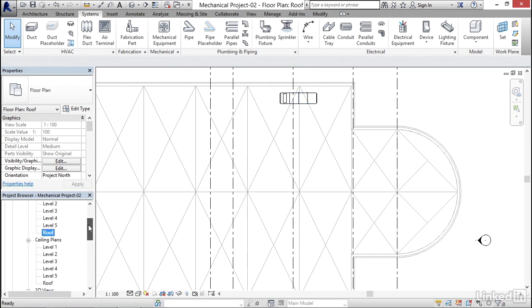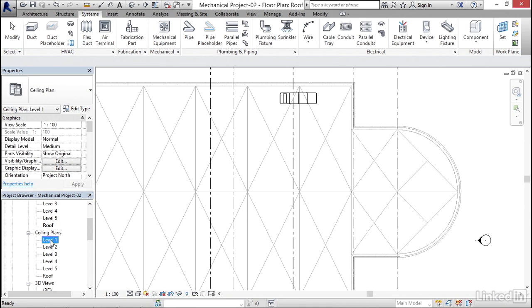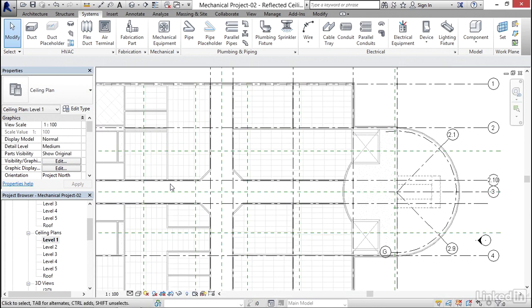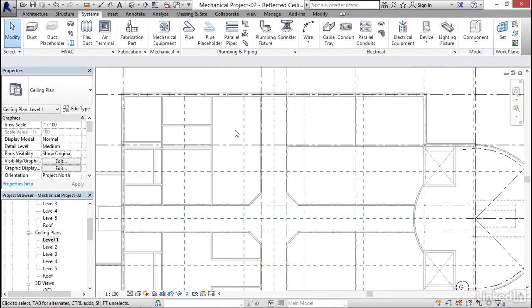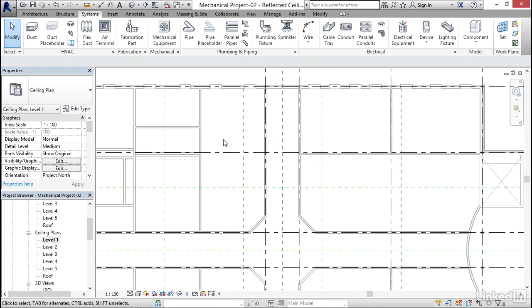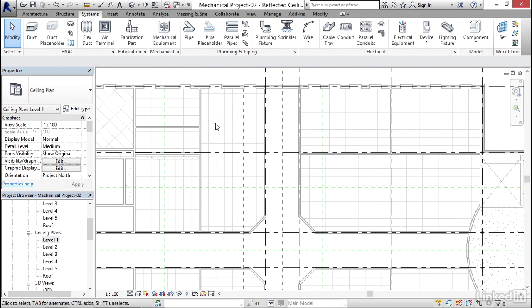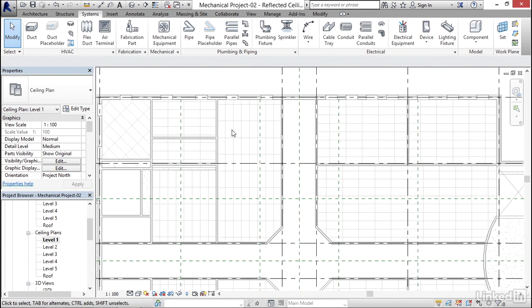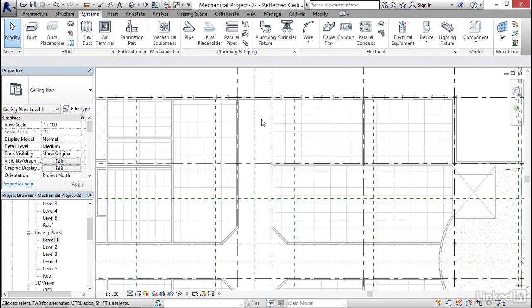We've got this in here. Now I want to go down to my ceiling plan level one. I like to hit my ceiling plan when I'm putting in my VAVs just because I like to see where there's a hard ceiling or where there's a suspended ceiling. Generally you want to put it somewhere where you can access it without having to cut a hole through some gypsum.